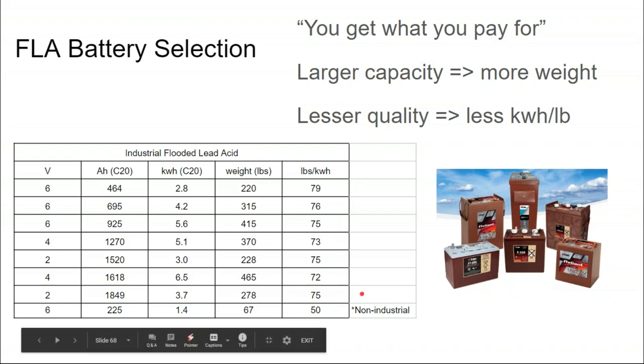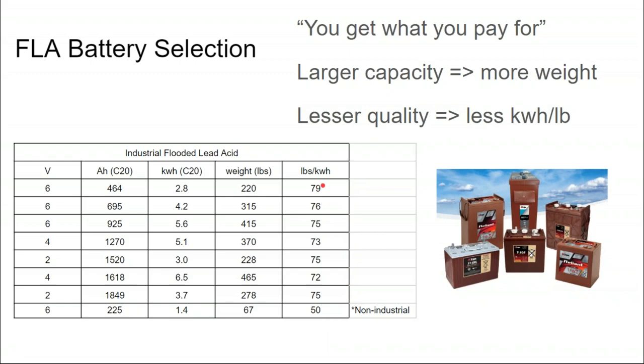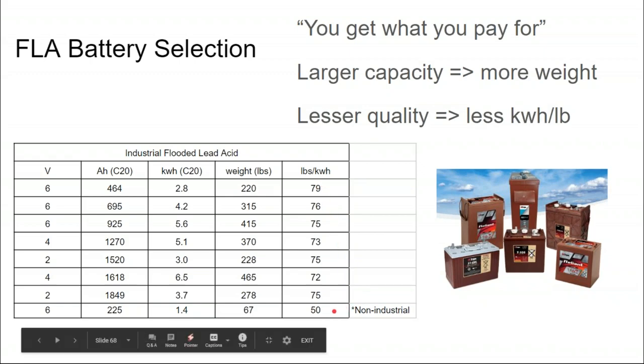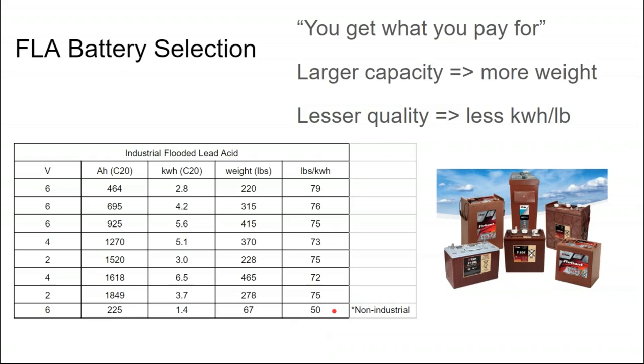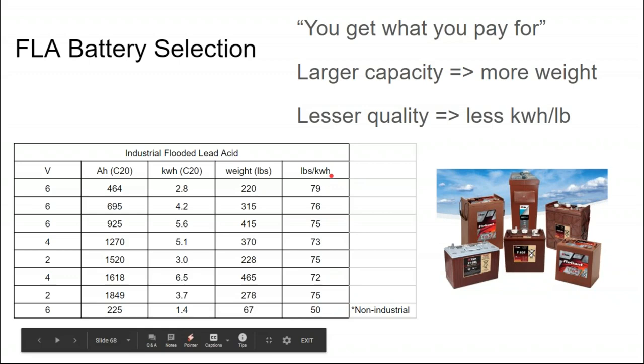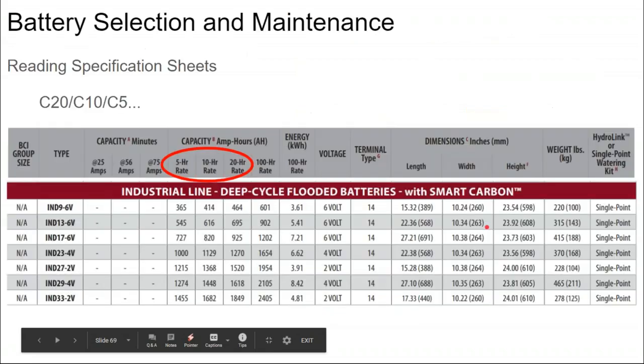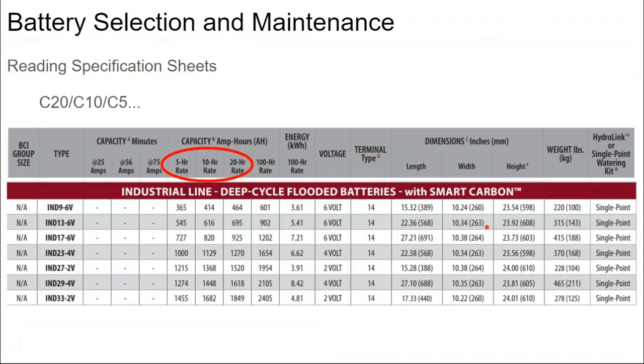But what I wanted to point out here is the weight per kilowatt hour of industrial flooded lead acid versus entry-level lead acid. It weighs about 50% more per kilowatt hour of storage than the premium or renewable battery line. The industrial flooded lead acid is substantially higher quality in terms of their cathodes and anodes - what goes inside the box - and that translates into a longer life, more cycles.